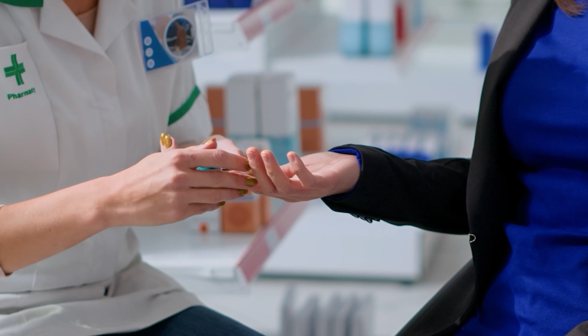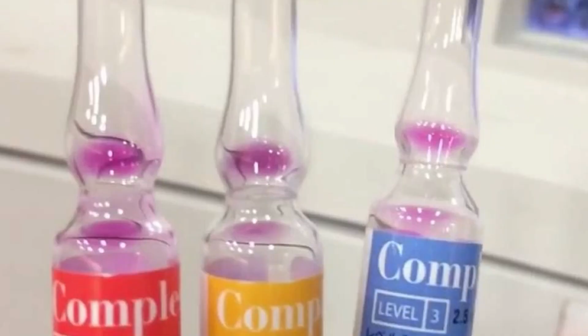For the NBRC exam, we need to focus on the arterial blood gas analyzer, because federal regulations require that analyzer be proven at least twice a day—every shift, which could be every 8 to 12 hours, sometimes 3 times a day—to confirm it's reporting accurate results. To accomplish that, we inject a fake blood material called a quality control material into the blood gas machine.